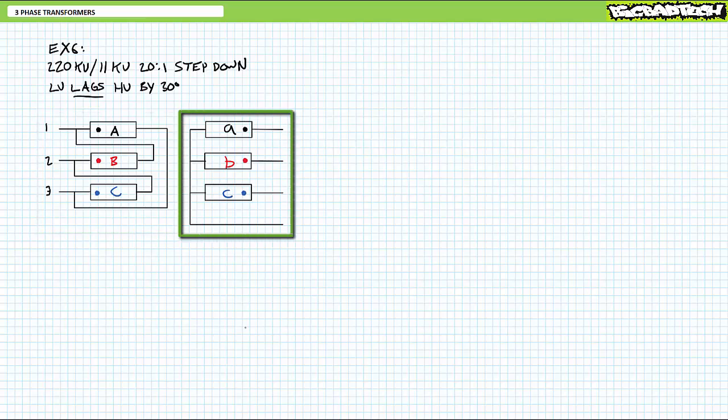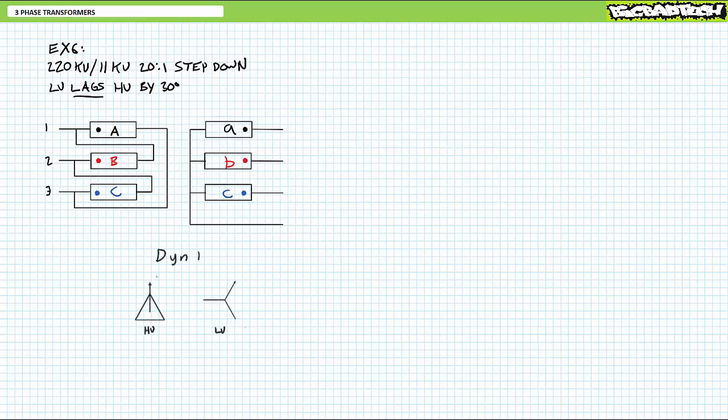The low-voltage secondary appears to tie together all the non-polarity ends of the three windings and bring this out as a fourth neutral wire. Understandably, this is a Y-configured low-voltage secondary with a neutral, so you got lowercase yn. Thus, the nomenclature would indicate that this is a DYN1 transformer.